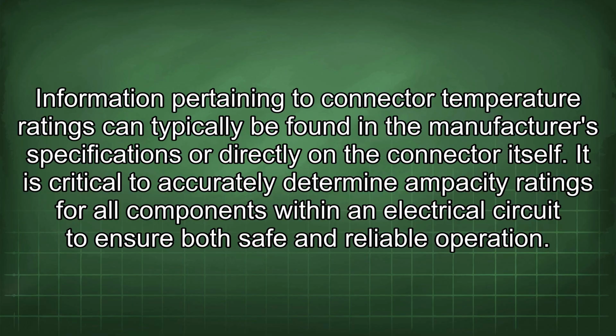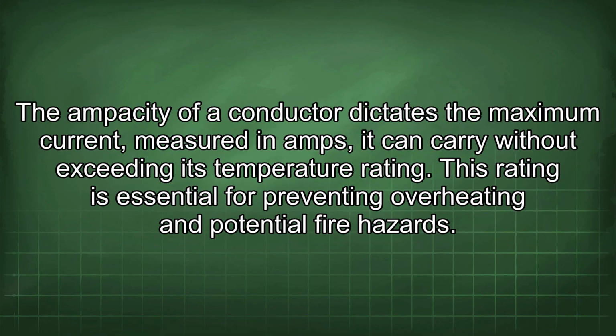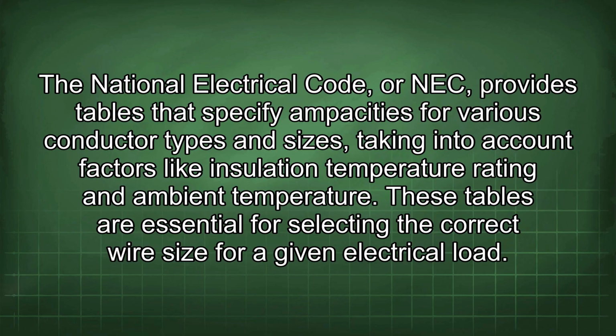It is critical to accurately determine ampacity ratings for all components within an electrical circuit to ensure both safe and reliable operation. The ampacity of a conductor dictates the maximum current, measured in amps, it can carry without exceeding its temperature rating. This rating is essential for preventing overheating and potential fire hazards. The National Electrical Code, or NEC, provides tables that specify ampacities for various conductor types and sizes, taking into account factors like insulation temperature rating and ambient temperature. These tables are essential for selecting the correct wire size for a given electrical load.